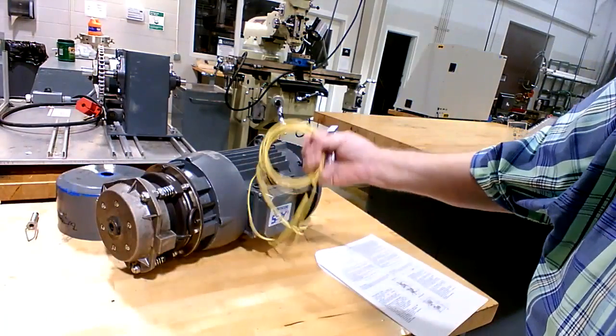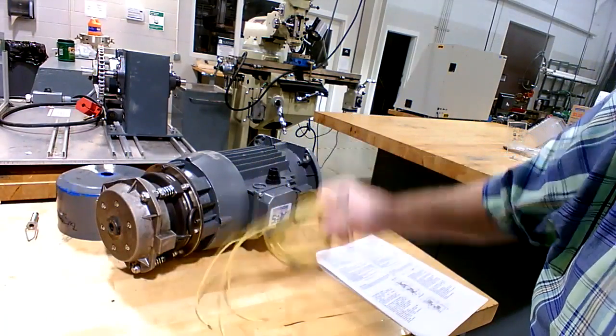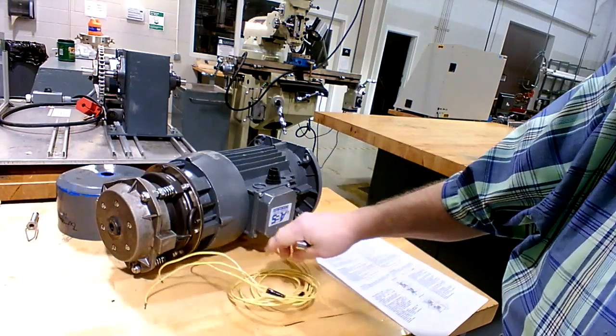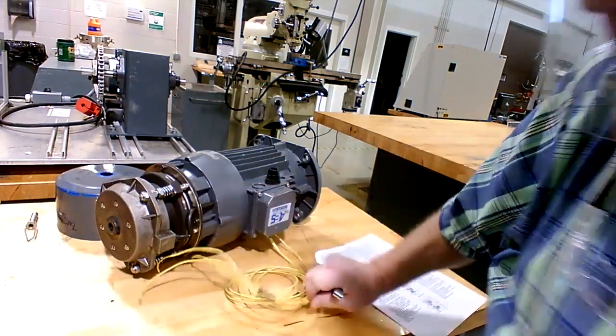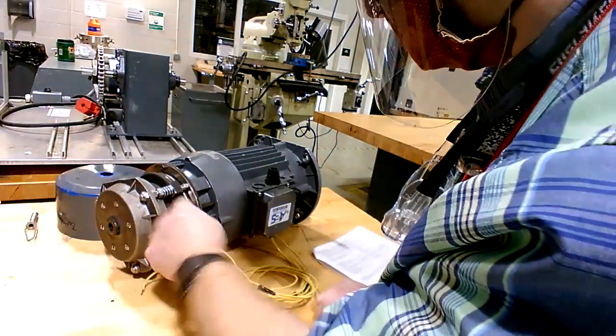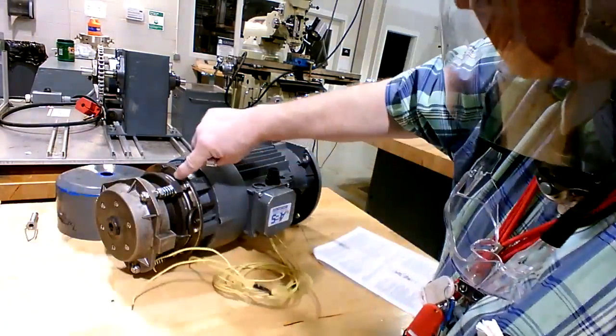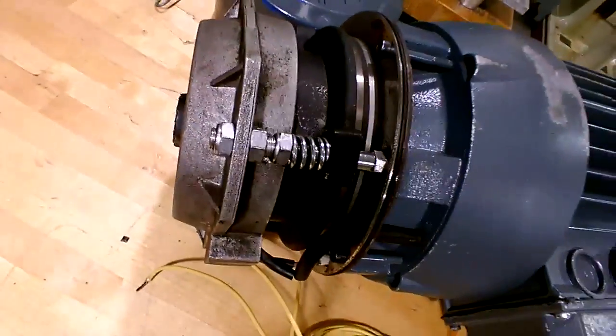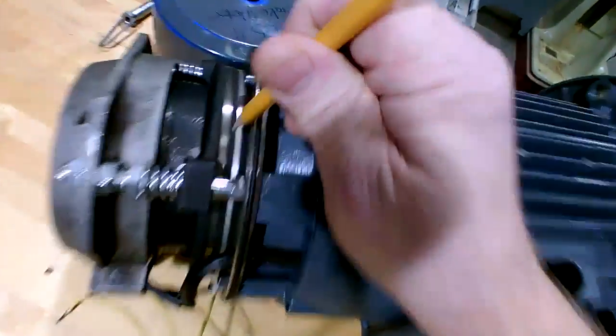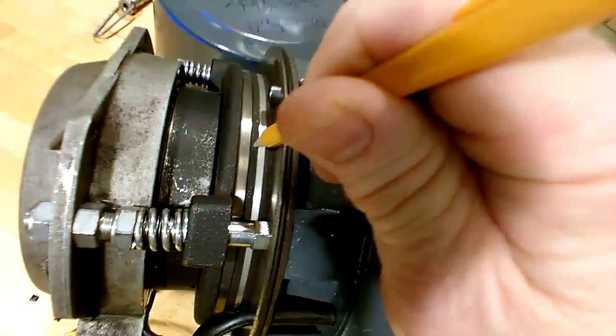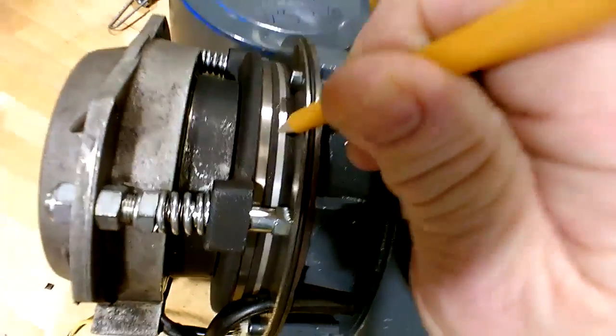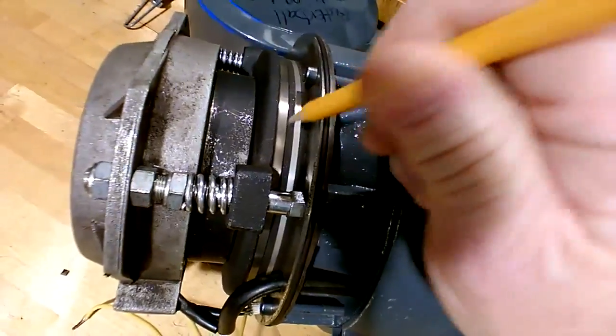When you energize it and put three-phase 480 volt on this thing, it does a couple things. It energizes a coil that pulls against the spring and allows a little gap in there, which I'll set with a feeler gauge. It'll set a gap between the metal plates and that friction pad. You have a friction pad in there that'll rotate, and we've got to produce a gap of 10 thousandths.